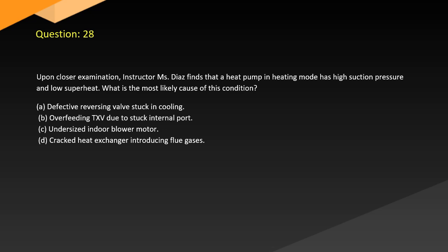Question 28. Upon closer examination, instructor Dias finds that a heat pump in heating mode has high suction pressure and low superheat. What is the most likely cause of this condition? A. Defective reversing valve stuck in cooling. B. Overfeeding TXV due to stuck internal port. C. Undersized indoor blower motor. D. Cracked heat exchanger introducing flue gases.